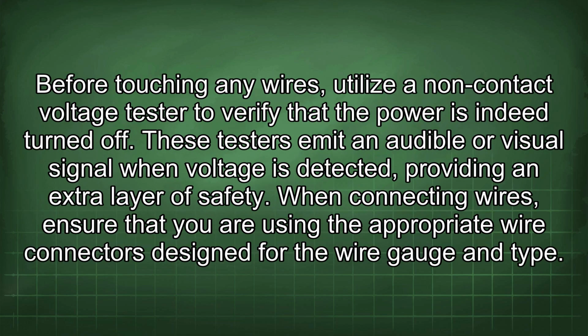Before touching any wires, utilize a non-contact voltage tester to verify that the power is indeed turned off. These testers emit an audible or visual signal when voltage is detected, providing an extra layer of safety.